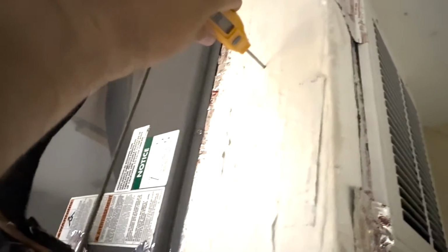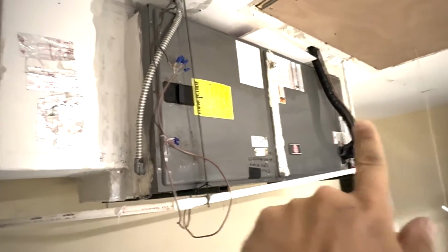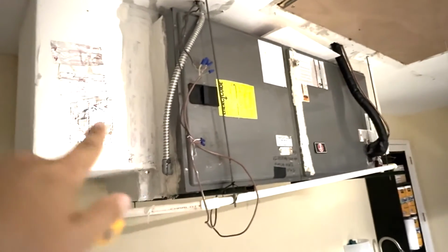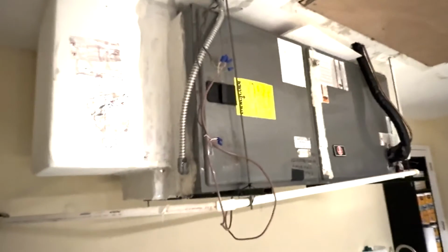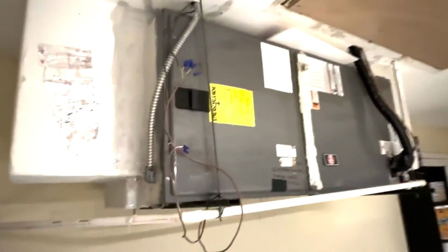So say that temperature was 78. Then I'm going to go to the supply side of the system, and you might already see a little hole in your supply side plenum anyway, and you're going to stick it in this side. The temperature difference between those two should be between 17 and 20 degrees ideally. So if it was 78 in my house, it should be going across that coil and coming out at about 17 to 20 degrees colder, so between 58 and 61.